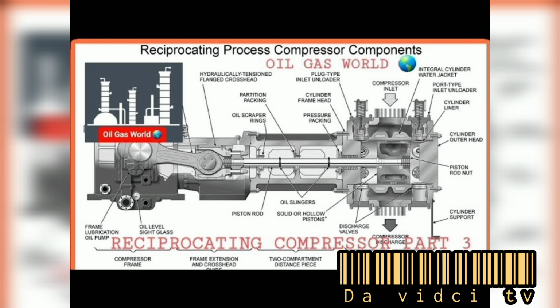A variation of the smaller, skid-mounted, engine-driven compressor is a larger, engine-driven version in the form of the integral engine compressor. See Figure 3-4. The compressor and the engine share a common frame and crankshaft. When the engine cylinders are vertical or in a V configuration and the compressor cylinders are horizontal, the machine is called an angle engine compressor. Reciprocating compressors are used for the direct reliquefaction of vapor boiled off due to heat inleak.